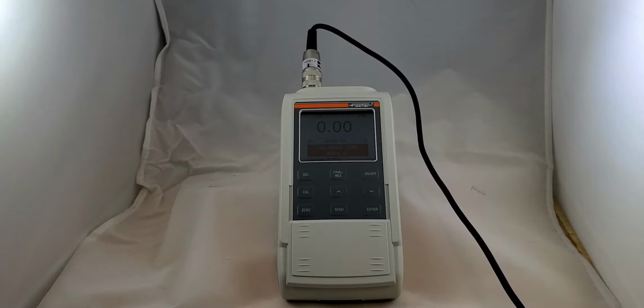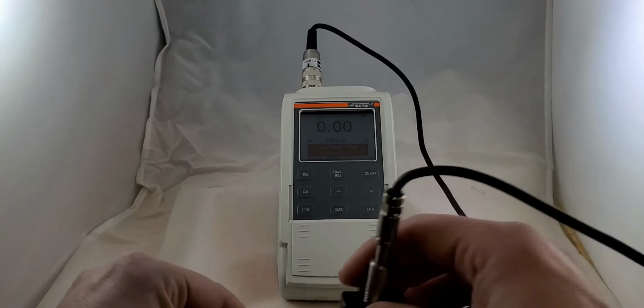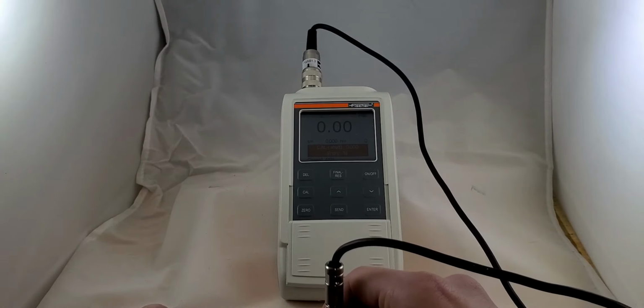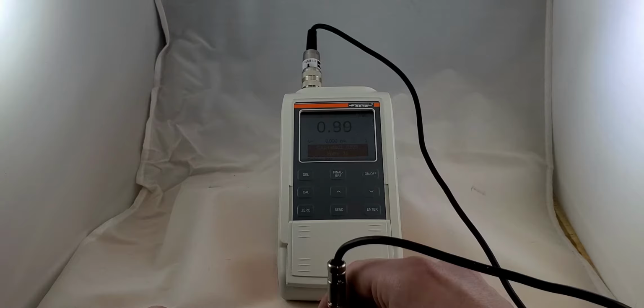This is going to be your low end calibration foil. I like starting with the low end so that way it works out logically in my head. I do the low, I do the high, then we test the middle. So again, we're going to do 5 measurements on our low foil.